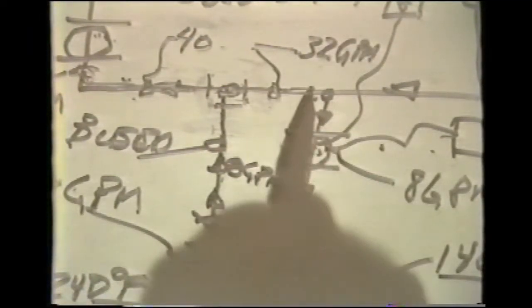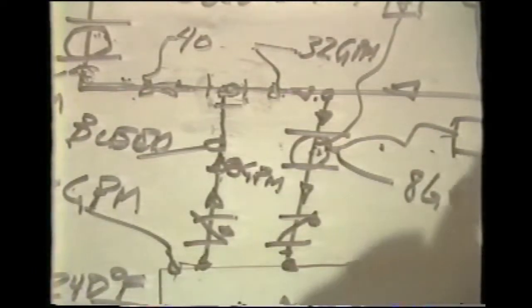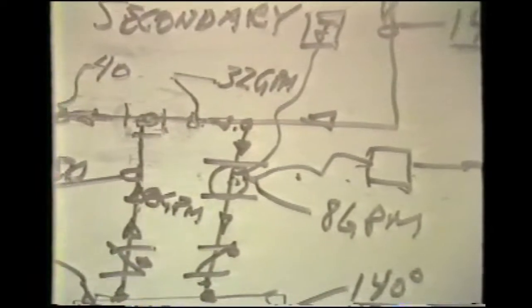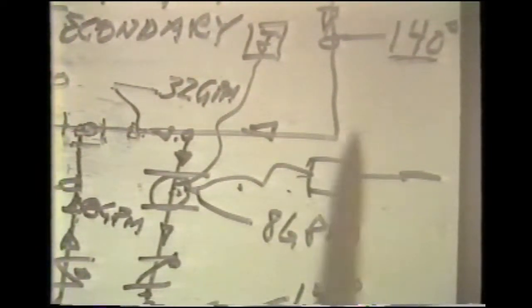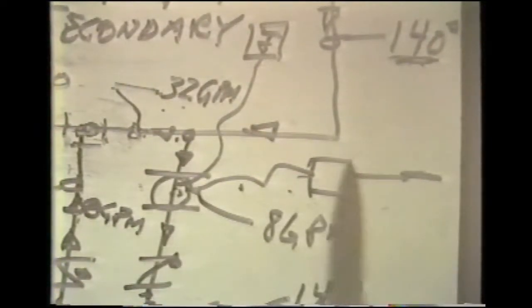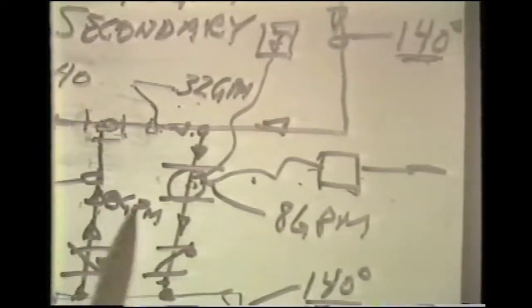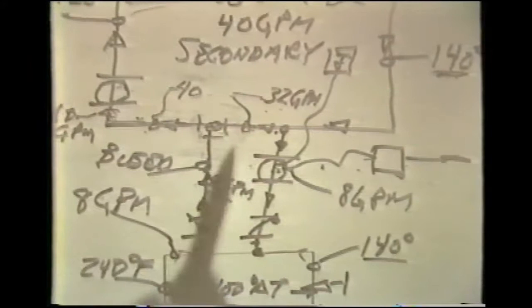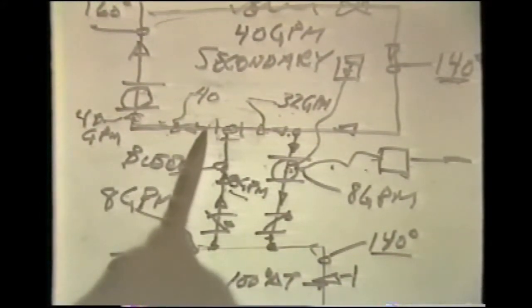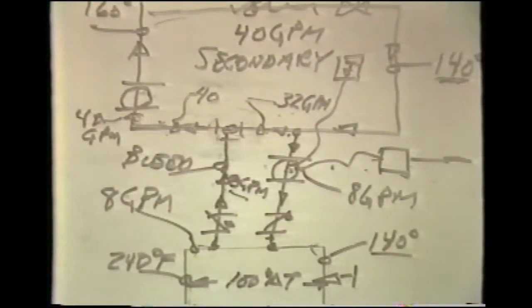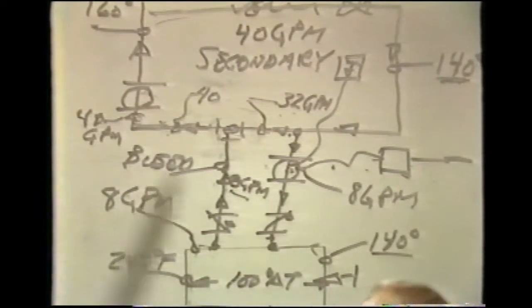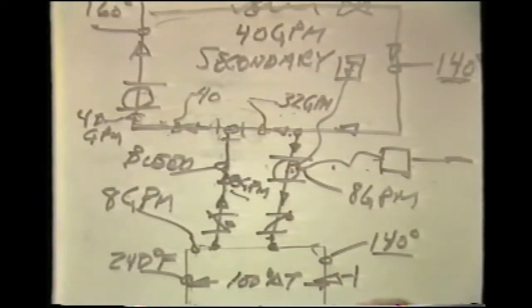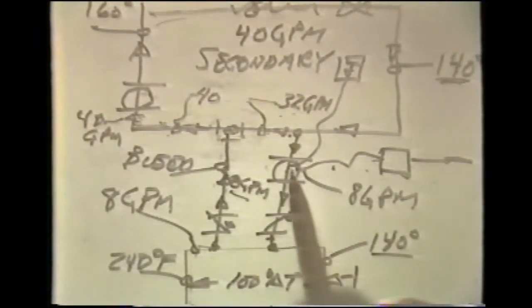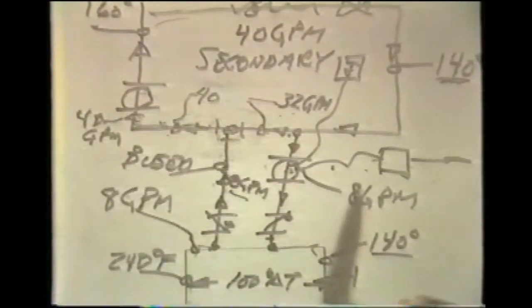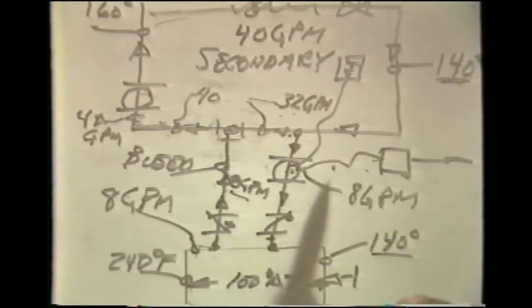The bypass water flowing into that T must be at the water temperature of 140 degrees. So what we have happening then is that we have 32 gallons per minute of water at 140 degrees, mixing with 8 GPM of flow at 240 degrees, providing a mixed water temperature of 160 degrees at 40 gallon per minute flow rate. This is a very, very simple application of injection pumping that has been widely used and works well because the B&G booster pump can stand continuous cycling in terms of injection without any difficulties at all.